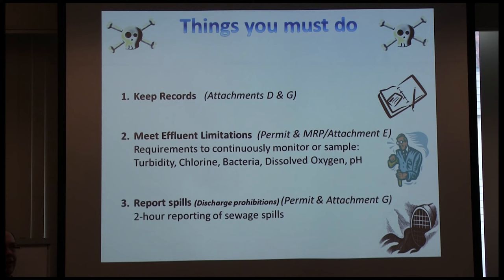We've been in dry years, but now El Niño is coming. All it takes is a big two-by-four getting in the sewer, a big clog, a sewer break — you have flooding in the streets and water going into a creek. It must be reported. You have to estimate the amount of water that went out, and report within two hours of becoming aware of a sewer spill.